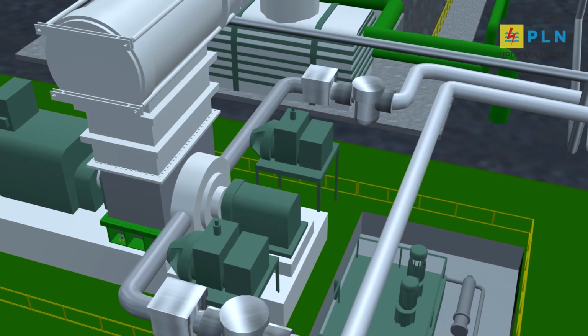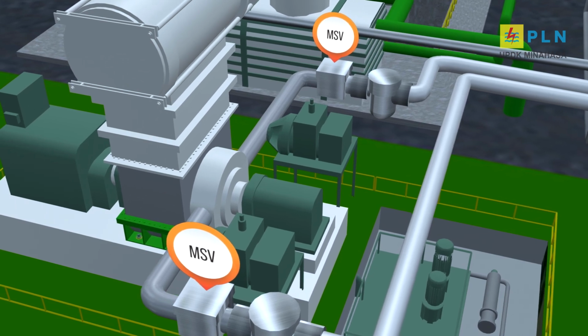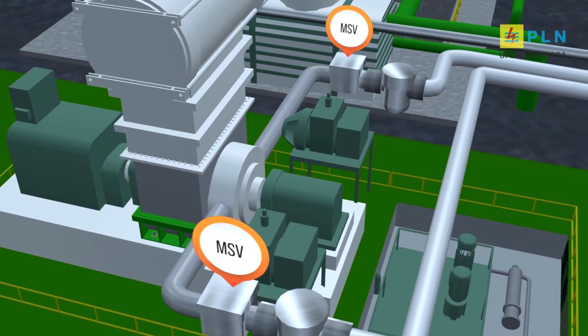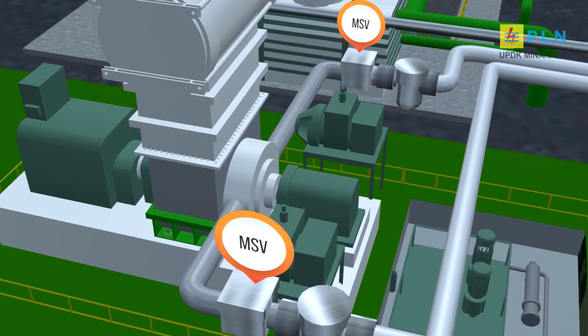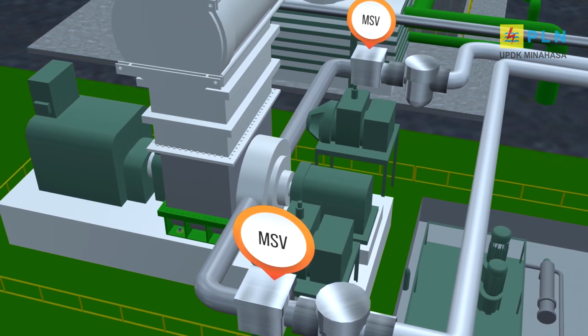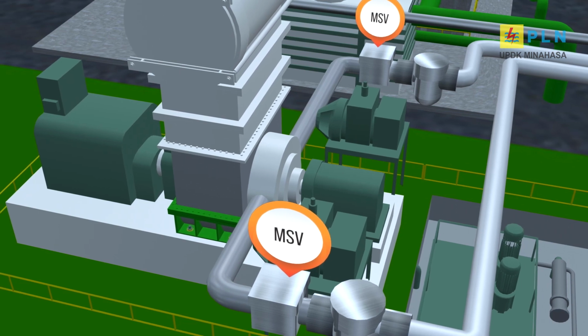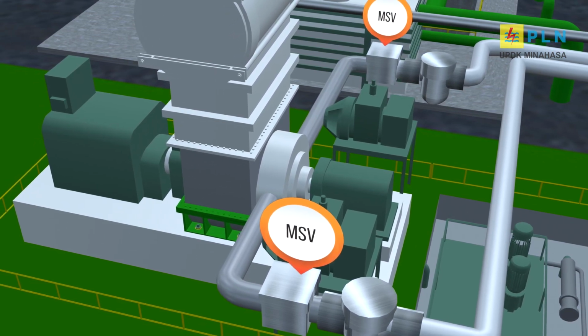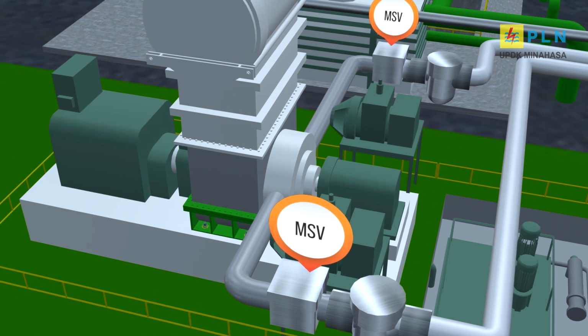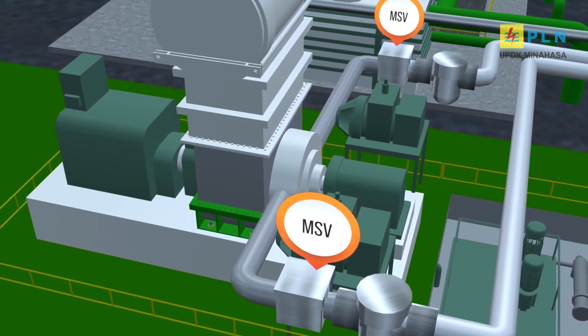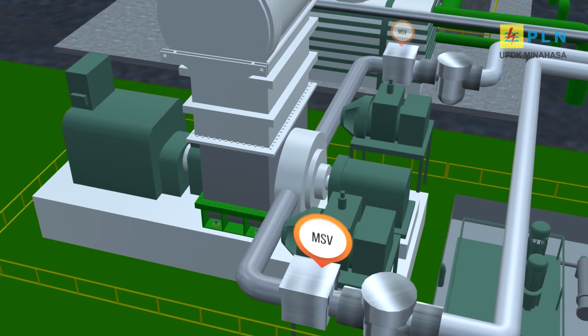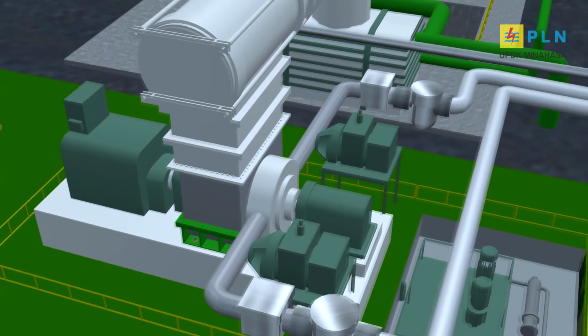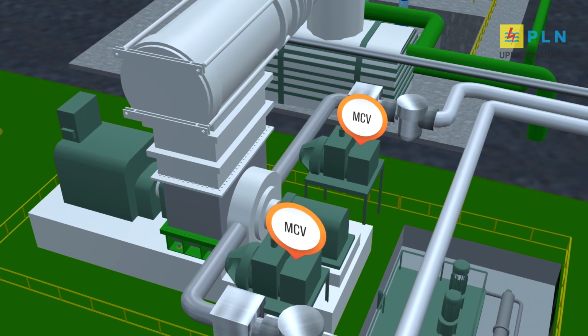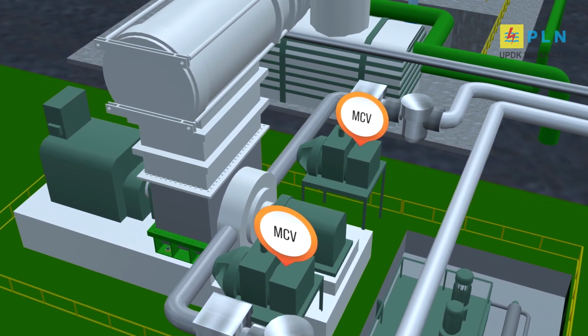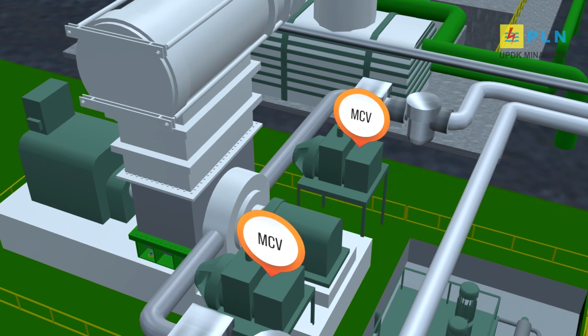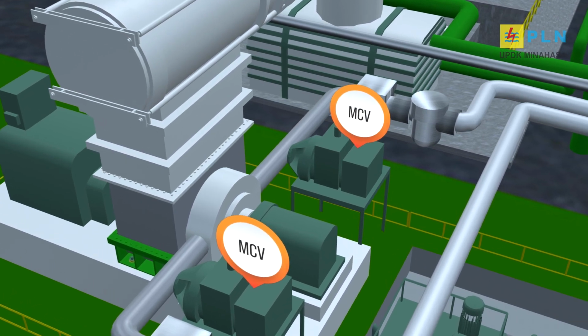After the strainer, the steam passes the main stop valve, which operates normally open. This MSV functions as a safety valve: in the event of a disturbance that causes the MSV to trip or the unit to stop, it closes so that the steam will be held and not enter the turbine. Then after the MSV, the steam passes through the main control valve or MCV, which operates as a throttle, following the loading pattern on the turbine, or regulating the amount of steam flow that enters the turbine.